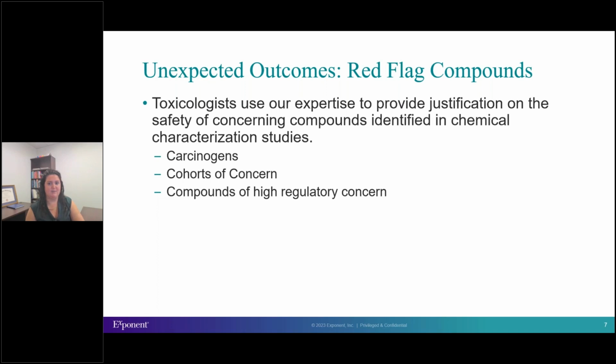for your risk assessment. So we have extensive experience and rely on agency-specific guidance, as well as our published standards, which we love the new ISO 10993 Part 17 for actually including carcinogenicity risk assessment guidance, so that way we can assess the clinical risk to patients for those carcinogens, as well as cohort of concern members.